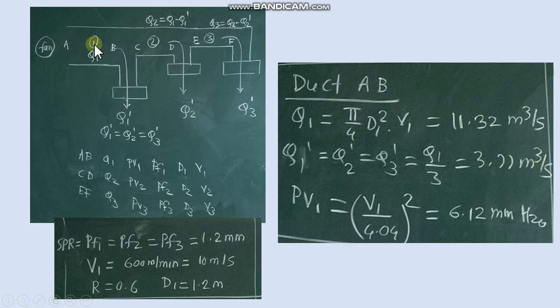Then in the main duct dynamic pressure PV1 we calculate. Now we go for the next duct CD. Where Q2 we can obtain now by subtracting this value from the Q1, 11.32. We get Q2.